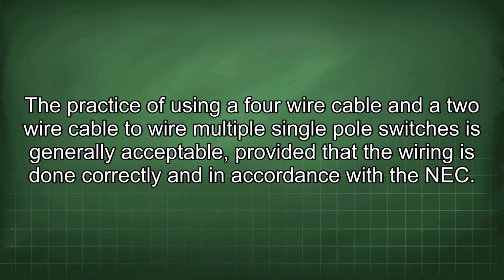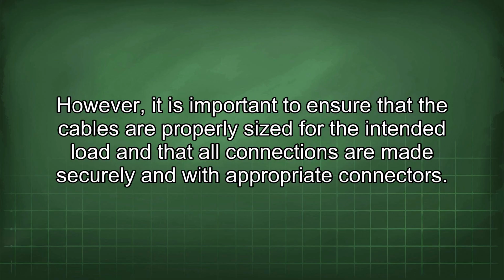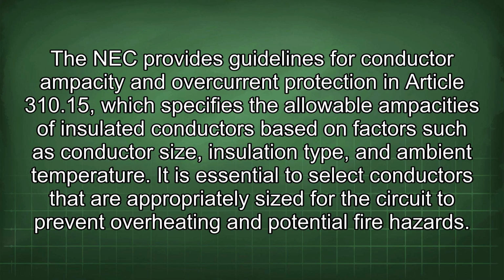The practice of using a 4-wire cable and a 2-wire cable to wire multiple single-pole switches is generally acceptable, provided that the wiring is done correctly and in accordance with the NEC. However, it is important to ensure that the cables are properly sized for the intended load and that all connections are made securely and with appropriate connectors. The NEC provides guidelines for conductor ampacity and overcurrent protection in Article 310.15, which specifies the allowable ampacities of insulated conductors based on factors such as conductor size, insulation type, and ambient temperature. It is essential to select conductors that are appropriately sized for the circuit to prevent overheating and potential fire hazards.